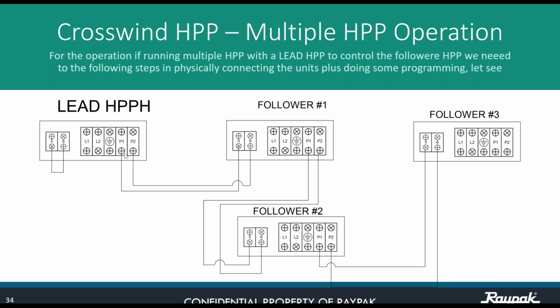From P1, P2, we run two wires to the next heat pump, follower number 1, and make the connection on the 5, 6. It's like we are bringing the automation to this point, but this is not automation. It's P1 and P2, and we continue P1, P2 to the 5 and 6 of follower number 2, and so on, P1, P2 to follower number 3, until whatever units you might have. You might have 10, you might have 15, whatever you want. You can make that connection like this.